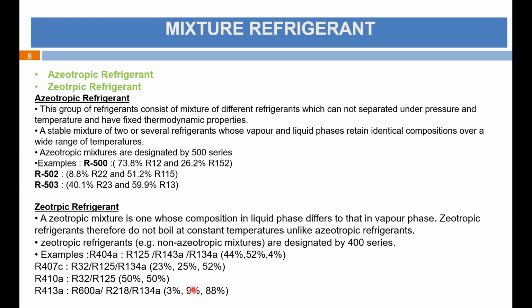So their property is that they are very stable mixtures of different refrigerants whose vapor and liquid phases retain identical composition throughout the temperature range. So R500, R502, R503 are refrigerants where the composition of the two refrigerants does not differ based on the temperature. So the composition remains fixed. They are a very stable kind of mixture.